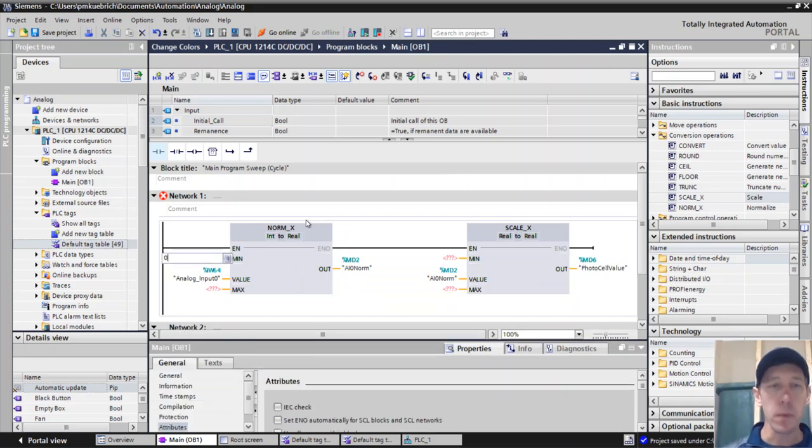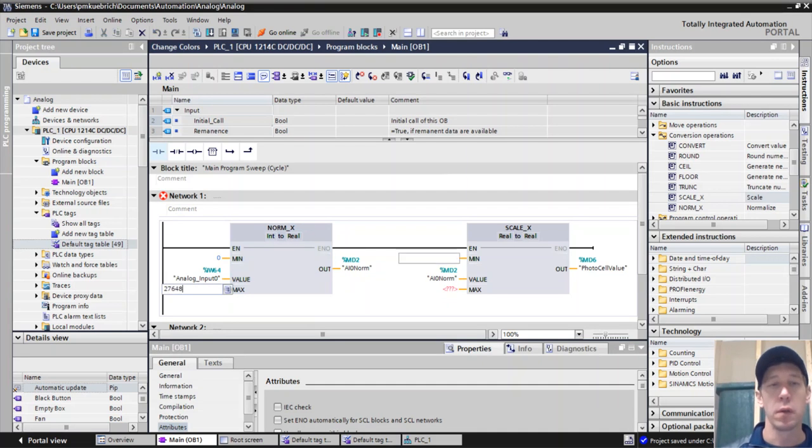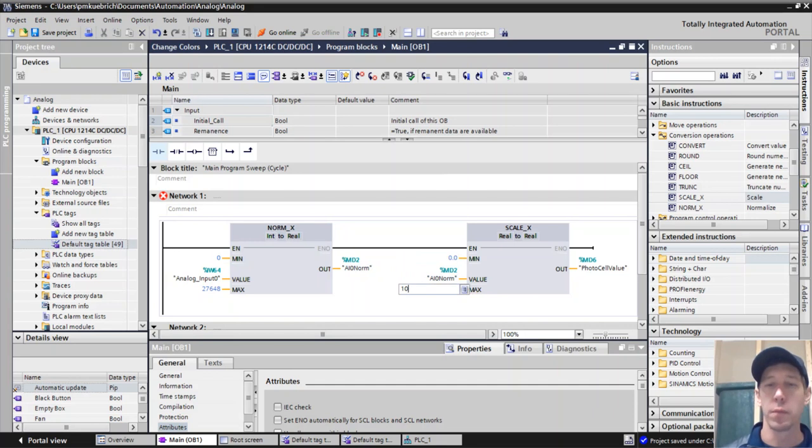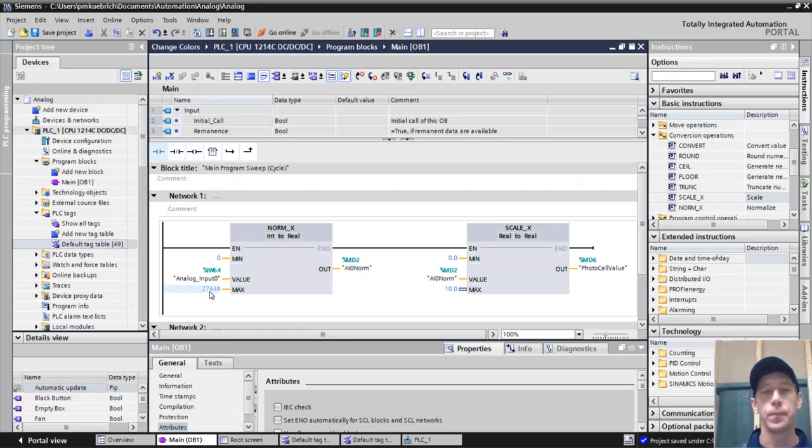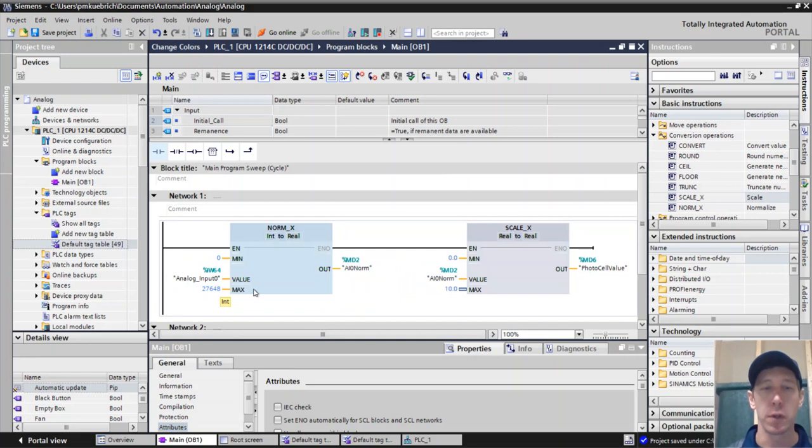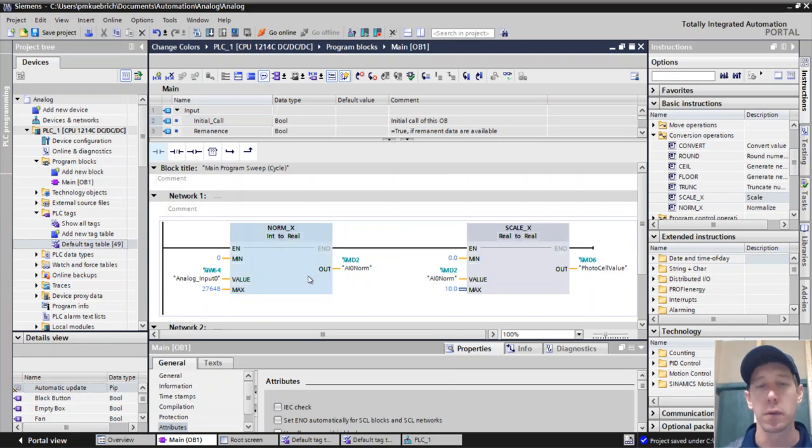And so minimum and maximum, I'll do it quick right now. And then I'll tell you in a little bit about where these values actually come from. But minimum is 0, 27,648 is our maximum for our normX. And then our scaleX is 0 to 10.